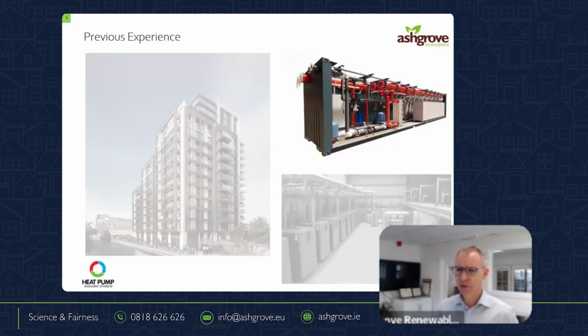Then we do containerized modular heat pumps. So we've done those up to 2 megawatts. So the heat pumps inside in that there, you can't really even see them in that image, but they're 100 kilowatt modules and simultaneous heating and cooling. So if we're maybe refrigerating an abattoir, we can take the cooling, and from that, of course, we can produce heat, where we can heat hot water or maybe produce space heating for something else.